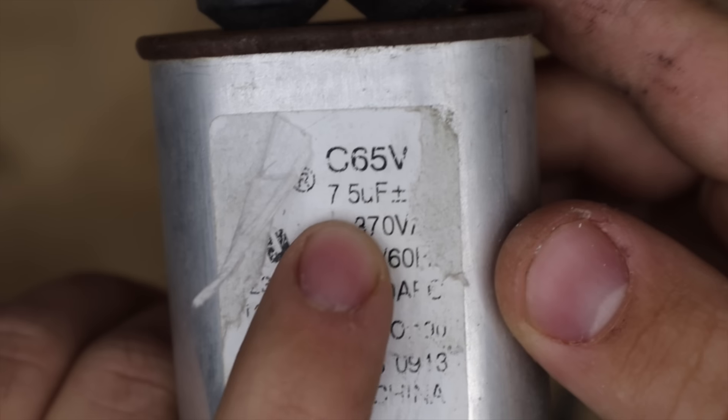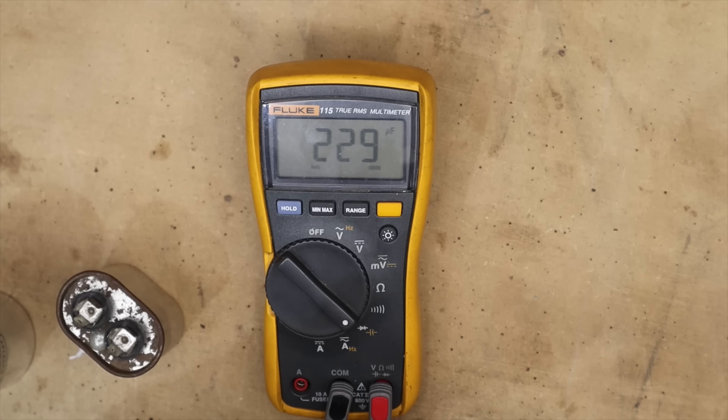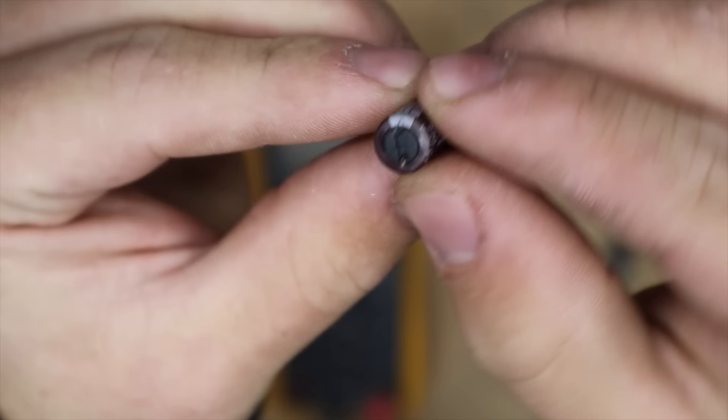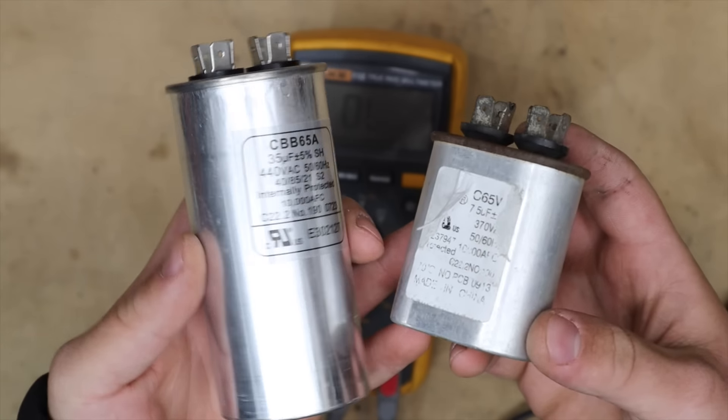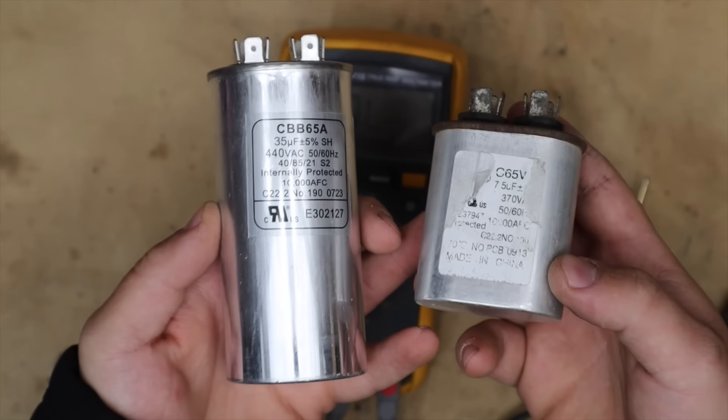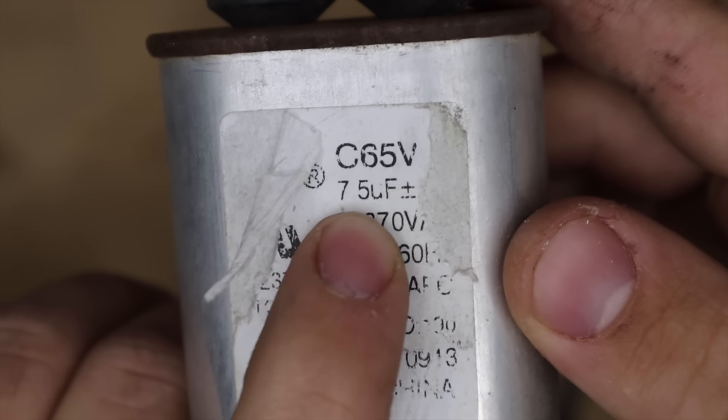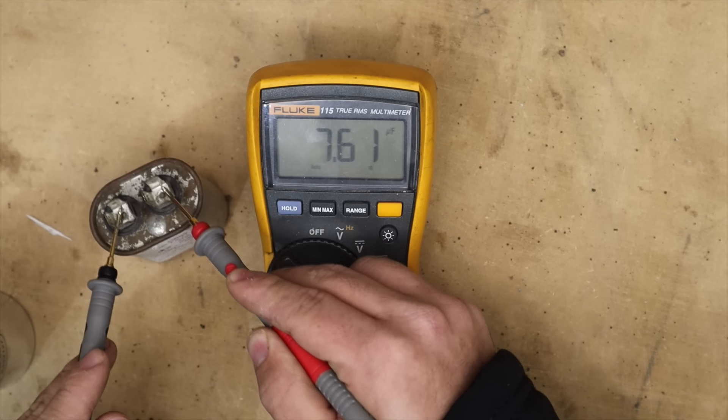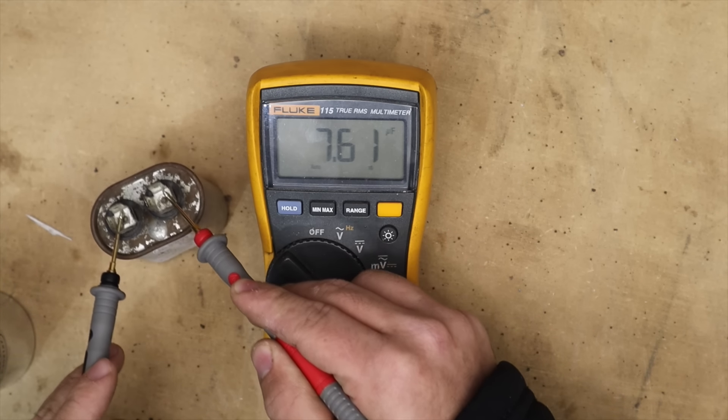Now usually farads are measured in the micro scale so you'll usually have this symbol meaning micro. This capacitor is reading 230 microfarads which is pretty standard. It will usually have some tolerances. We then have this one which is non-polarized at 7.5 microfarads with a five percent tolerance. If we test it we get a reading which is higher but it is within that five percent range.